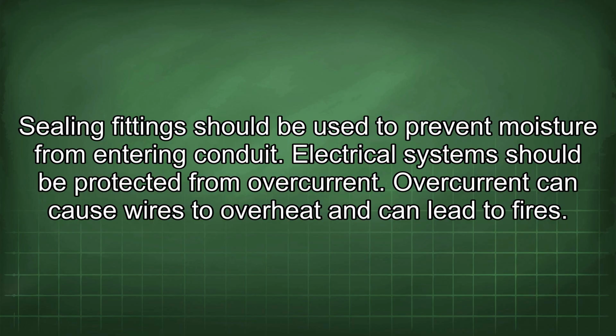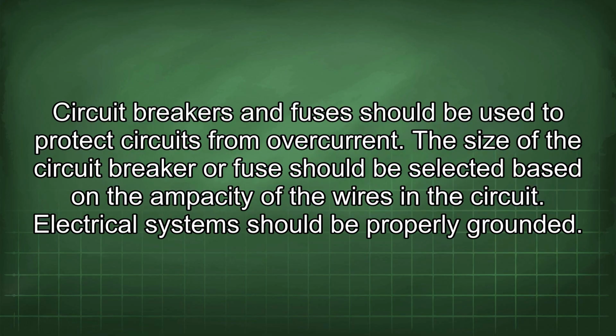Electrical systems should be protected from overcurrent. Overcurrent can cause wires to overheat and can lead to fires. Circuit breakers and fuses should be used to protect circuits from overcurrent. The size of the circuit breaker or fuse should be selected based on the ampacity of the wires in the circuit. The electrical system should be properly grounded.